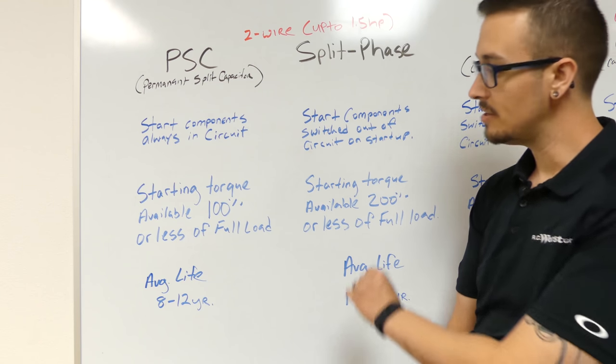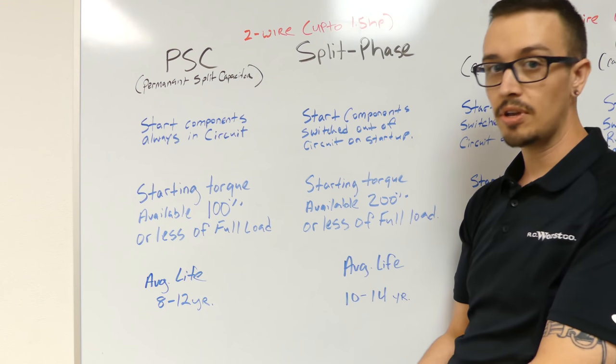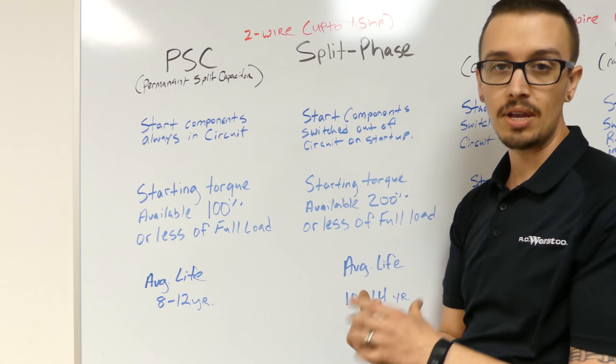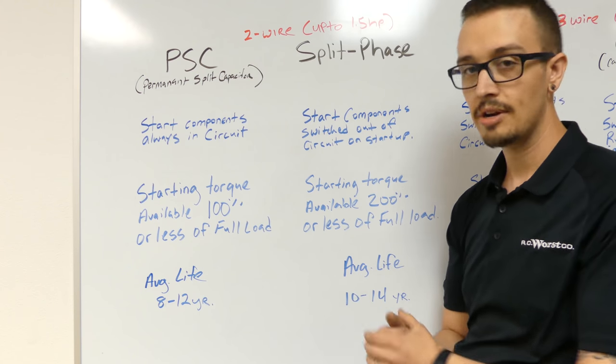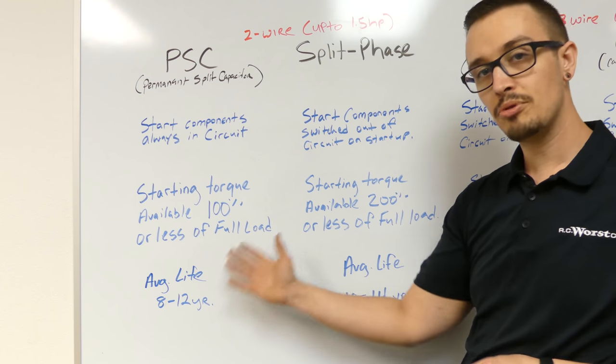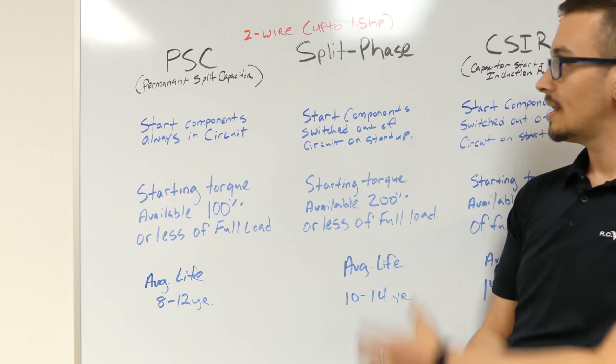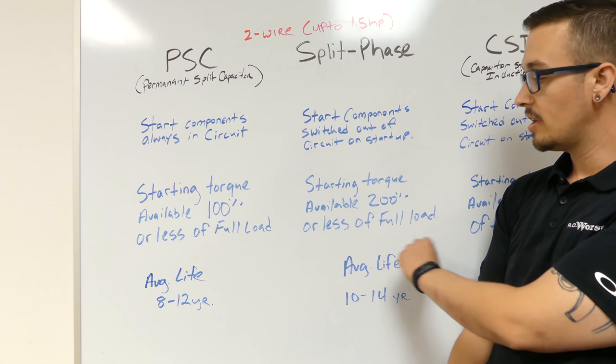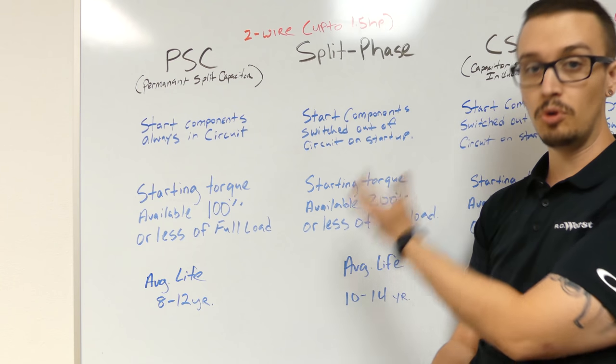And that actually brings us right into the starting torque available on these motors. Now these are just standard figures, not any specific manufacturer, because a lot of times this data is not published. So this is generic information. The starting torque available on a PSC motor is typically 100% or less of full load. And then when you're looking at a split phase motor, the starting torque available is generally 200% or less of full load.